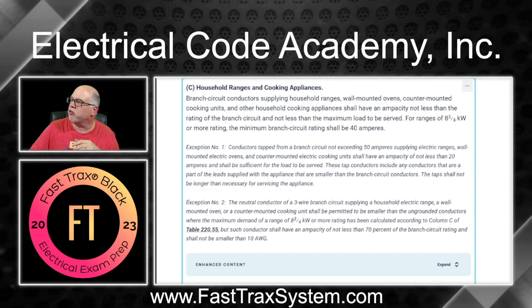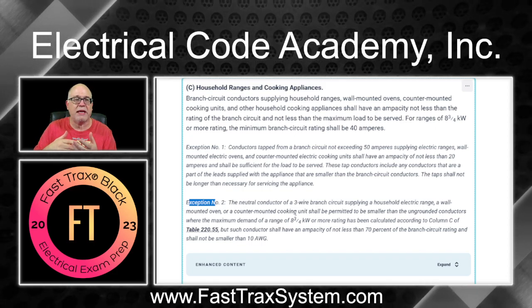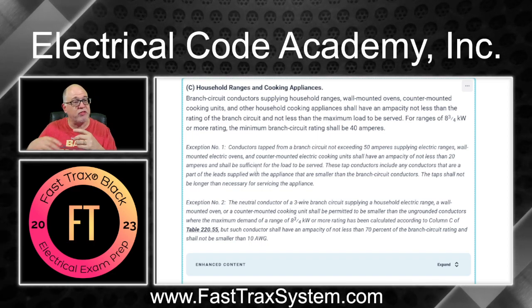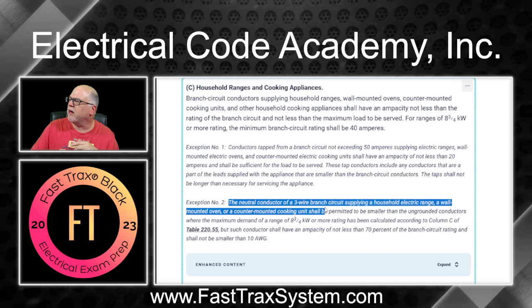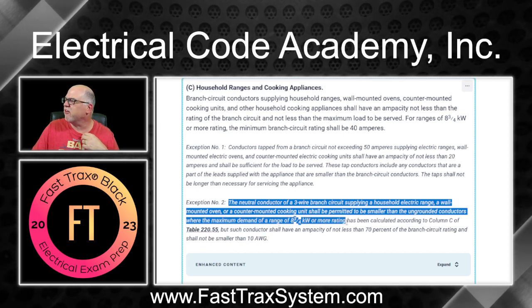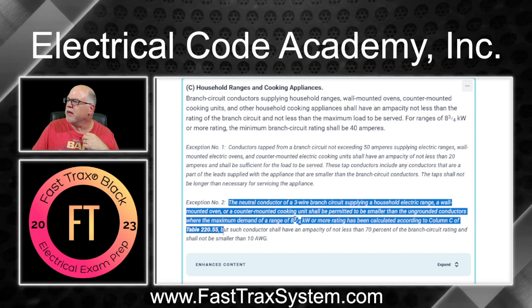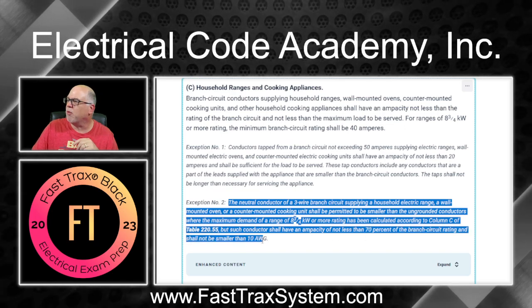There is an Exception Number Two that we're not going to cover in this video, because we're just talking about sizing the hot conductors. We will cover neutral applications in another video. But to briefly summarize: it reminds us that neutral conductors of a three-wire branch circuit supplying a household range, wall-mounted oven, or counter-mounted cooking unit shall be permitted to be smaller than the ungrounded conductors, where maximum demand is calculated per column C of 220.55, but not less than 70% of the branch circuit rating and not smaller than 10 AWG.